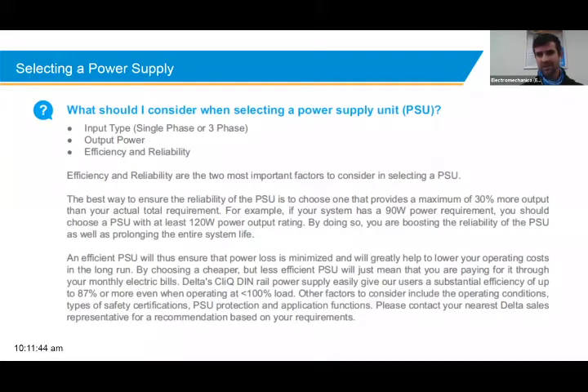To ensure good reliability in a power supply system, it's my rule of thumb and Delta's as well that you should always have at least 30% buffer in your power supply compared to your load. So in other words, a 90-watt load, you would want to go for a 120-watt power supply. This just makes sure that there's enough capacity from the power supply, and it does prolong the system life. So a great way to ensure reliability is just to add that extra 30% onto your actual power consumption in terms of your power supply output.